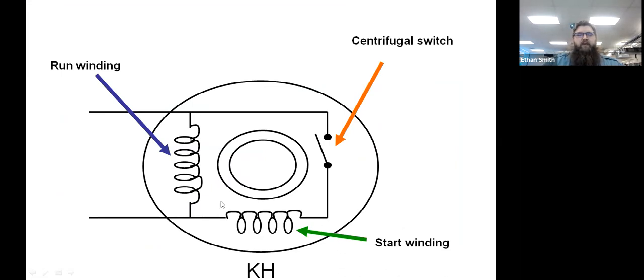And in this case, where we have our run winding, just like we did on our shaded pole motor, we also add a start winding. These start windings are arranged so that they're out of sync with each other. So you'll have a run winding here in the motor, and then a start winding that kind of nests off to the side of it. That gives the rotor a little more starting torque. It shoves it a little harder, gets things running a little quicker.